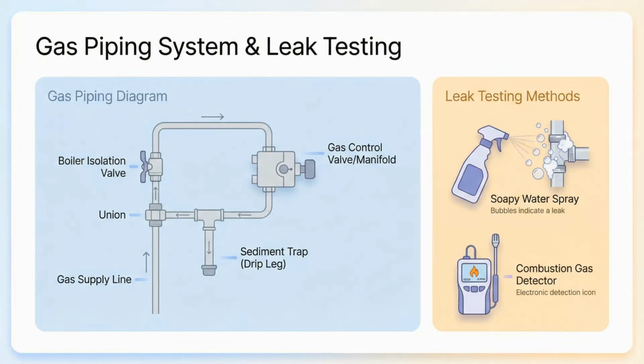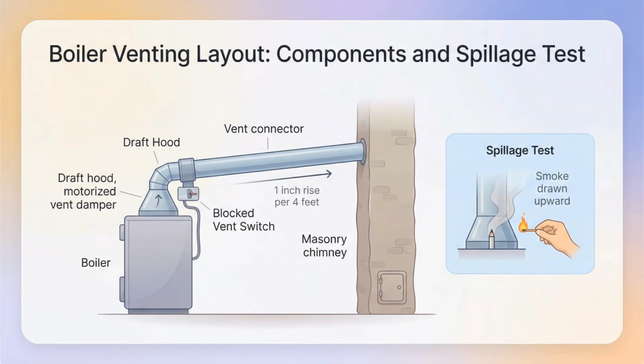On the gas side, the line must be sized correctly and meet gas code. When pressure testing, the boiler should be isolated and the piping tested for leaks. Leak checks are done with an approved gas detector or a soapy water test. Simple, visual, and effective. Manufacturers also show the required isolation valve, sediment trap, and union arrangement. Venting must follow the authority having jurisdiction and the manufacturer's vent material and sizing requirements.